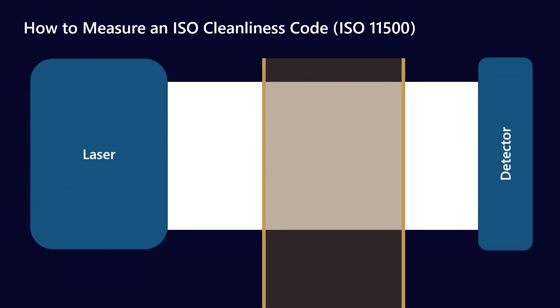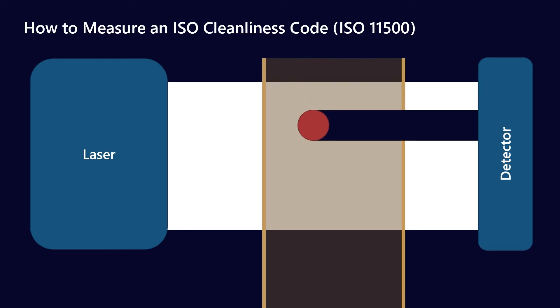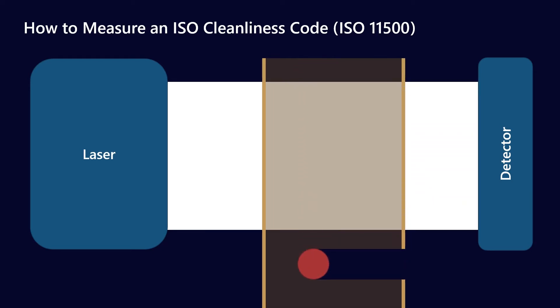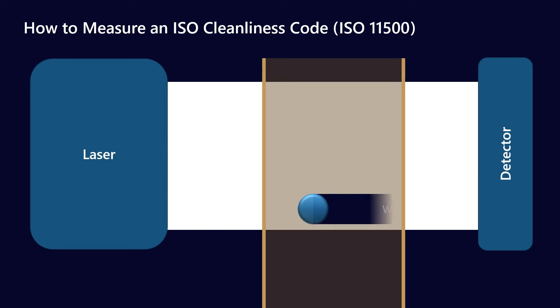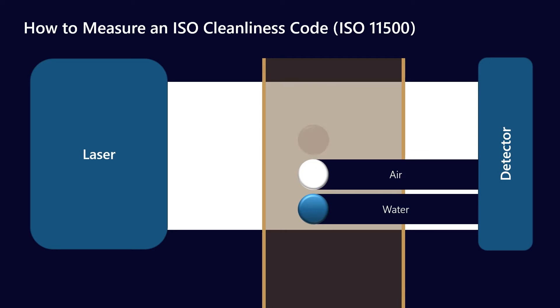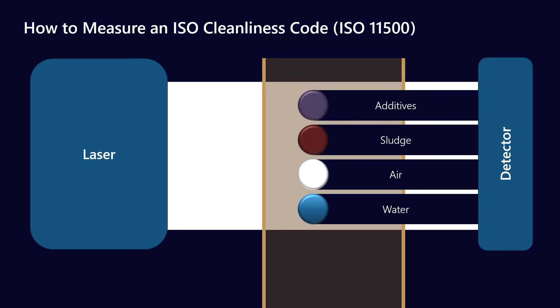Just to recap - I'll put a link in the description - ISO 11500 uses the light extinction method, so a particle crosses a laser beam and is picked up on the detector. The problem with this is that it can also pick up things such as water, air, sludge, and additives.